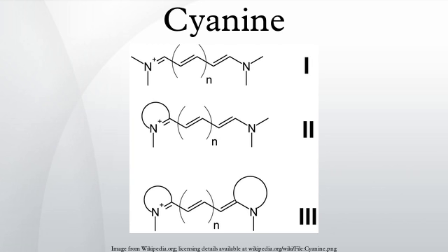Cy5 ozone susceptibility. In 2003, researchers at Rosetta Inpharmatics and Agilent reported in Analytical Chemistry that microarrays which used Cy5 were susceptible to intermittent data quality decrease caused by environmental ozone. Exposures to ozone levels above 5 to 10 ppb for 10 seconds were reported to decrease the reproducibility of Cy5 microarrays. Much higher levels of ozone were required to observe an effect in Cy3. There are devices that claim to remove ambient ozone levels but they have not been third-party tested.